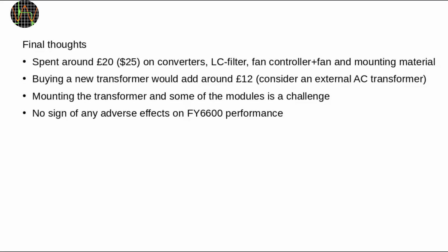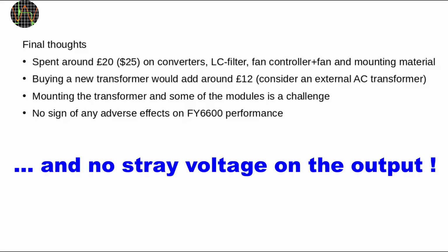If I had to buy one, I would consider getting an external one. They look just like ordinary wall chargers but produce AC instead of DC. Just make sure it's a properly rated isolation transformer. This would save a lot of space and mounting headache and lowers the temperature inside the unit even further. In my tests, I looked specifically for any issues affecting signal quality, but as far as I can tell, there's no difference to using the original power supply.